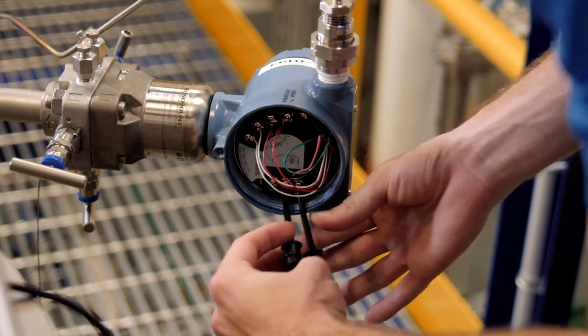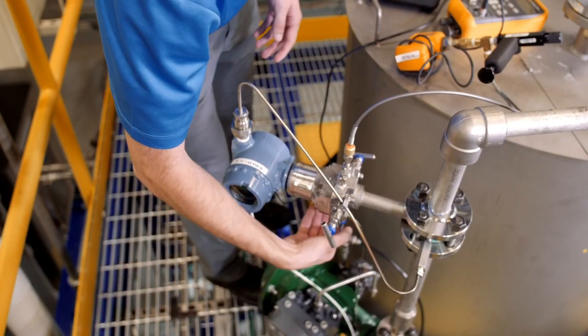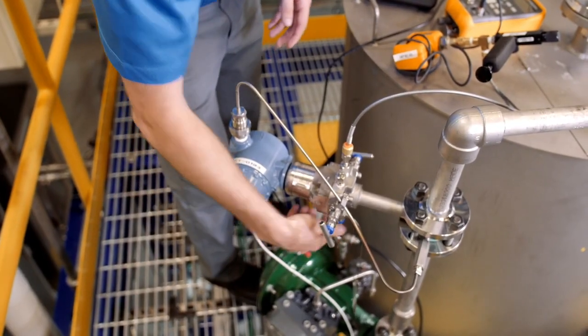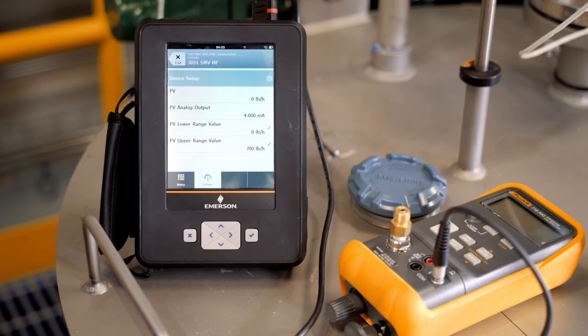The first calibration point will be a zero trim. A zero trim is a zero-based offset that provides a baseline for the measurement. For this reason, the equalize valve must be manipulated so that the high and low sides of the transmitter are experiencing equal pressure, or zero DP.